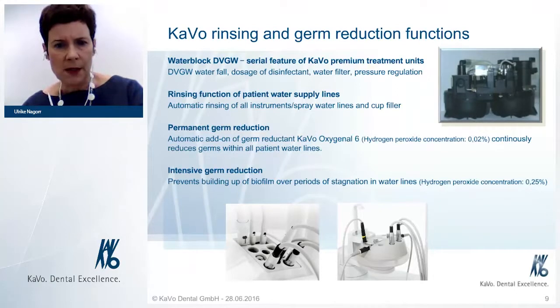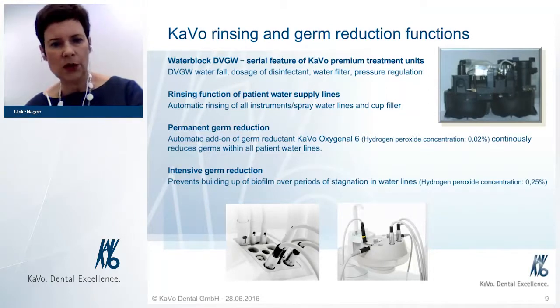The water block also takes over the function of germ reduction within the treatment unit, and it fulfills two different types of germ reduction functions. One is a permanent germ reduction function where a disinfectant, the KaVo Oxygenal 6, is added continuously into the water supply lines to reduce biofilm or avoid its build-up inside the very thin lines of the water supply tubings and instruments.